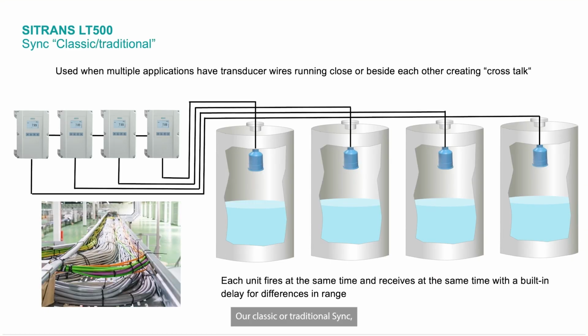Our classic or traditional sync, which you've been familiar with, is used when multiple applications have transducer wires running close or even beside each other, which could create crosstalk. So where you have applications with multiple tanks and multiple controllers and all of the transducer cables are running in conduit trays, all back to a control room or a central source where all of the controllers are held, this is where we like to use sync to ensure we don't have that crosstalk between the transducer cables.